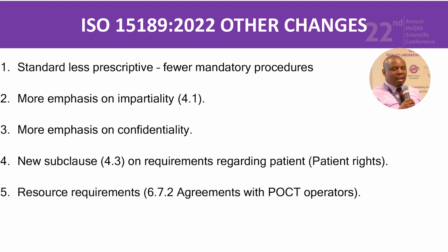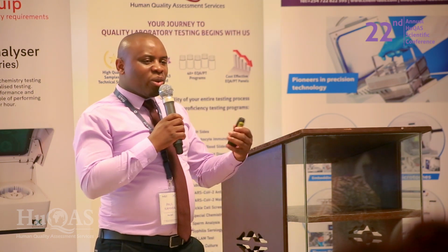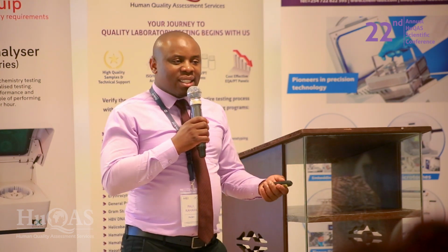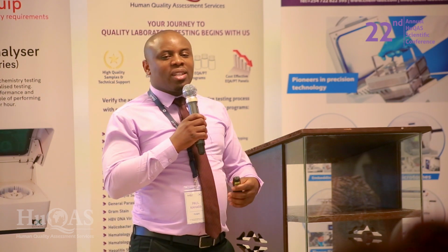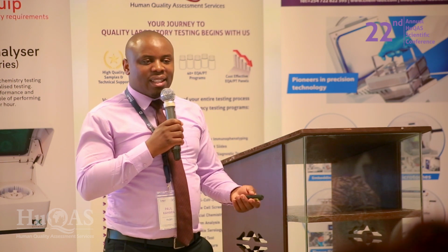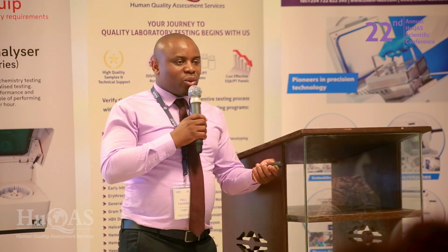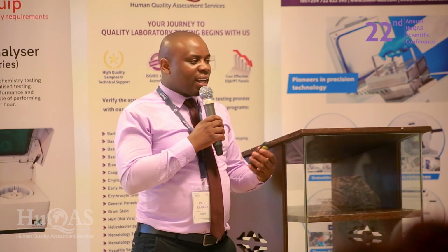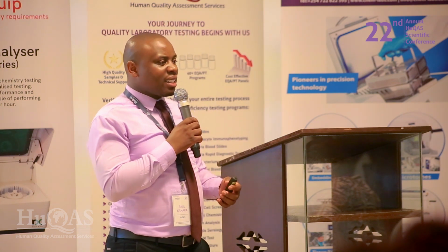In fact, the standard asks us to have an agreement document with all users of our point of care devices. I know this has been an issue in the past where we keep asking ourselves, do we want our nurses to handle these gadgets? Do we want our clinicians to handle these gadgets? Do we want the community health workers in the field to handle these malaria rapid testing kits? Now, if they have to, because sometimes we don't have a choice, in the ICU you will have our nurses handling the blood gas analyzers.